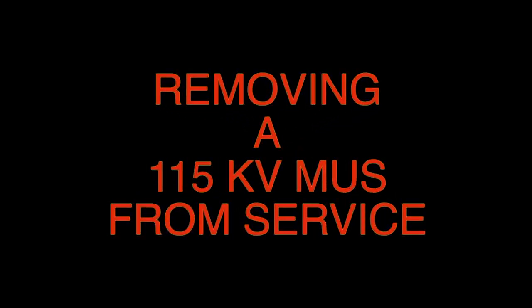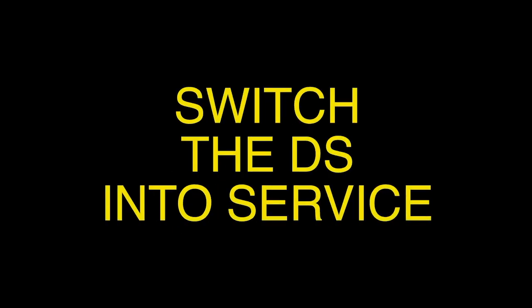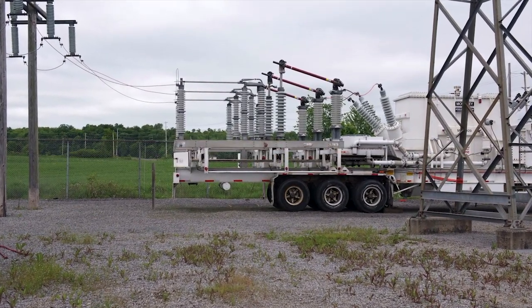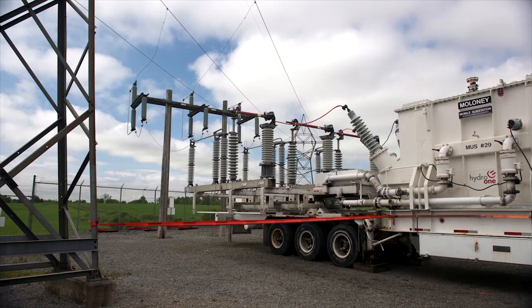A DGA sample must be taken from the main tank and ULTC compartment after the MUS has been placed into service, ideally between 24 and 48 hours, but due to resources and scheduling, between 4 and 72 hours is acceptable. We will now look at the steps for removing MUS-29 from service.